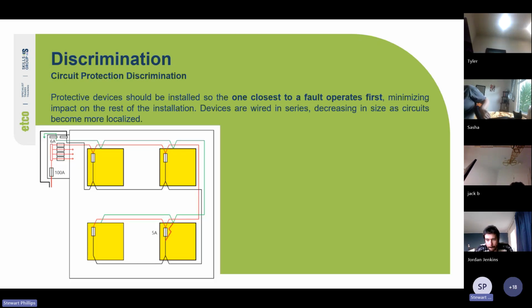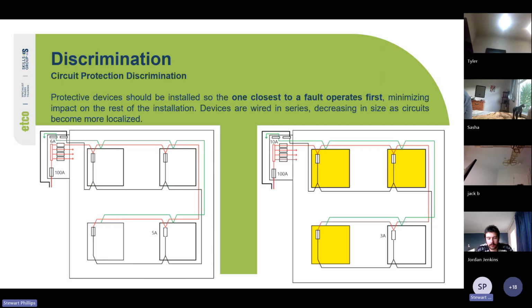So we look at the first example. We've got a 6 amp fuse, and then there's a 5 amp fuse in a room. But because they're so close together in rating, the 5 amp fuse and 6 amp fuse blow at the same time. However, if we were to decrease the fuse in the room to 3 amps and increase the one at the board to 10 amp, the 3 amp fuse would blow well before the 10 amp, so it would only take out the one room rather than all 4 at the same time.